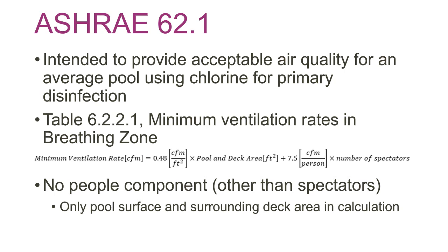Another note to make is that over the years there's been a lot of discussion whether it's dry deck or wet deck, because the deck area that is dry obviously isn't off-gassing chloramine. So it's up to the engineer to decide. The most recent version of the standard basically says that the engineer needs to determine the area that could possibly be wetted during occupied operation. You can play with those numbers in different ways, but the safest way to do it is to assume the pool and deck area is all used in that calculation. An exception might be a hotel where you had a seating area in the same space.